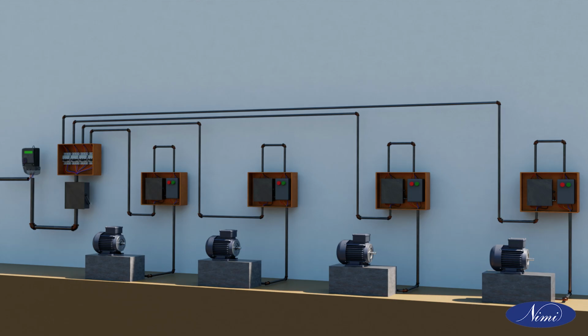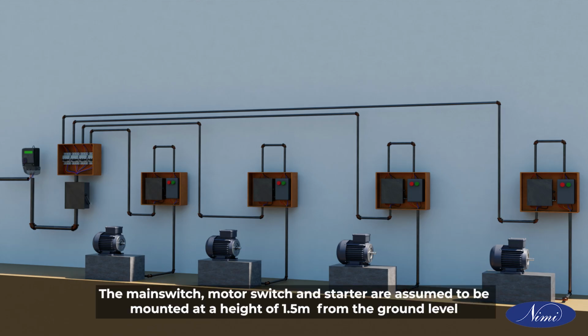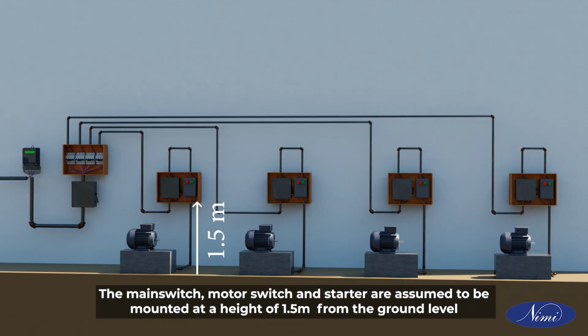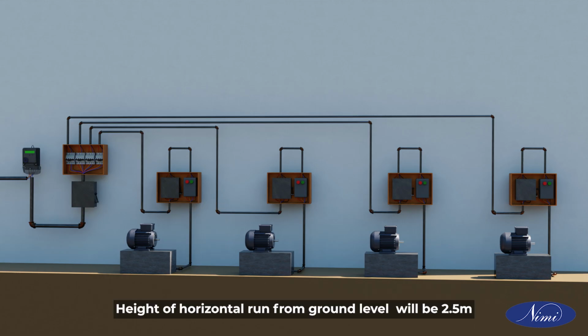Note: the main switch, motor switch and starter are assumed to be mounted at a height of 1.5 meter from the ground level. Height of horizontal run from ground level will be 2.5 meter.